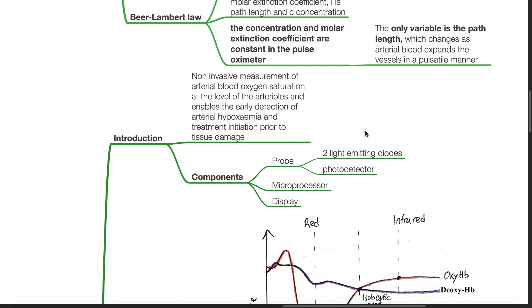The components of a pulse oximeter consist of a probe, which has two light emitting diodes and a photodetector, a microprocessor, and a display.